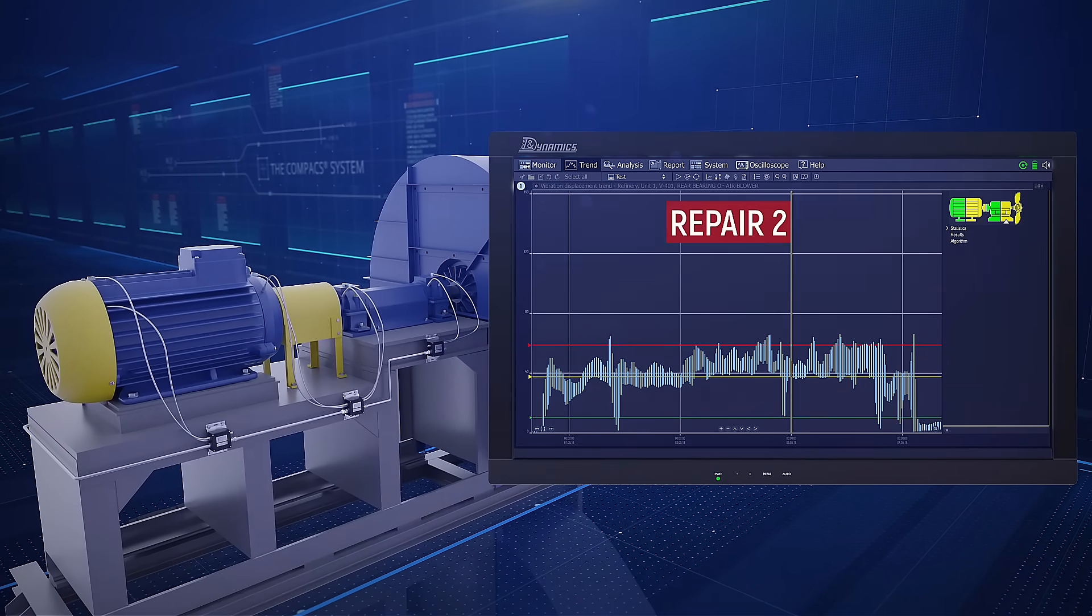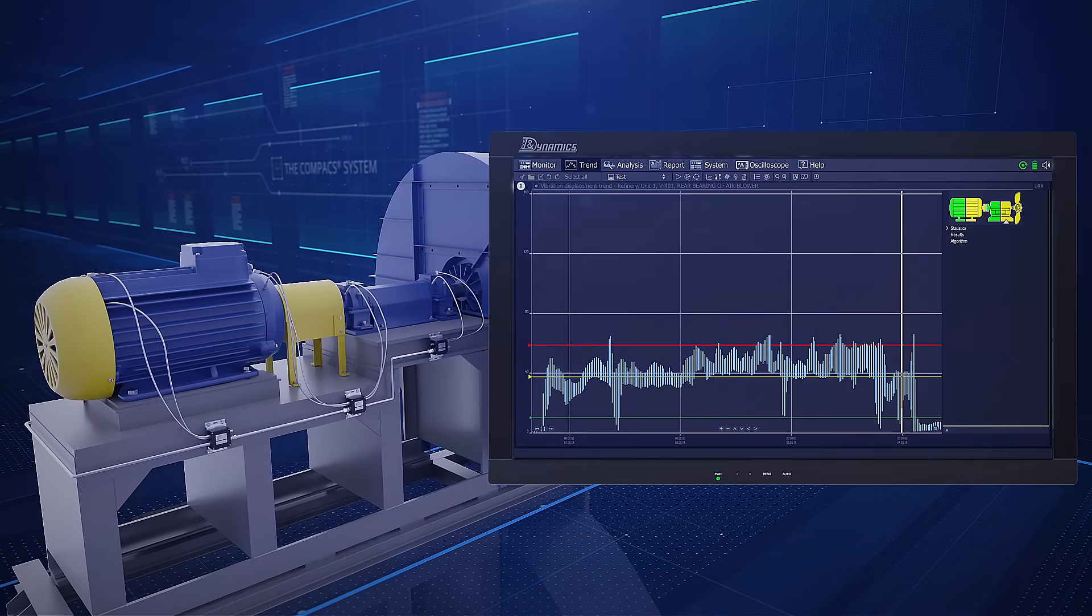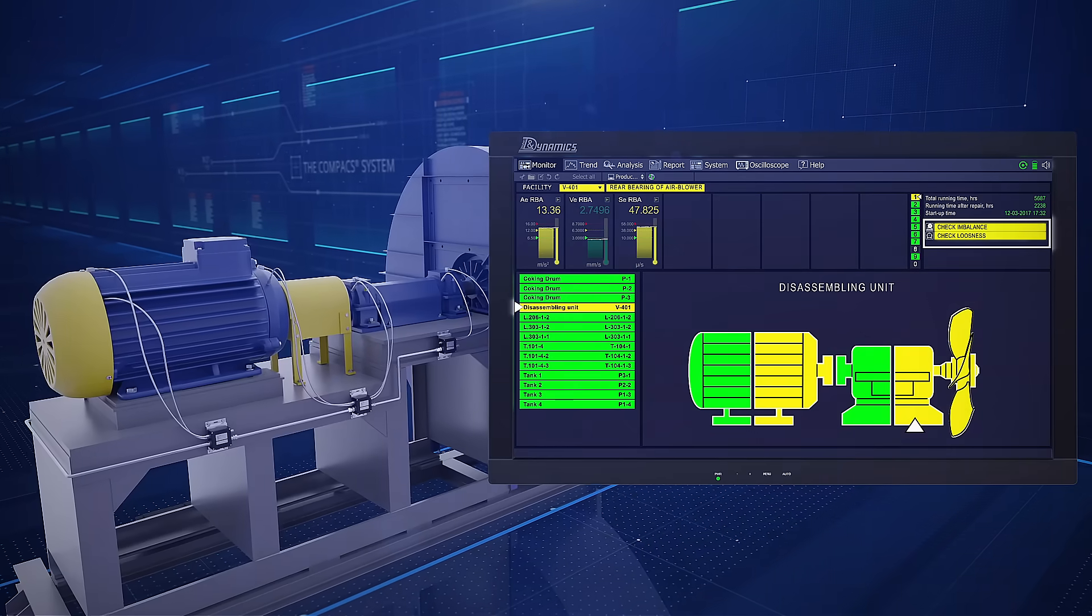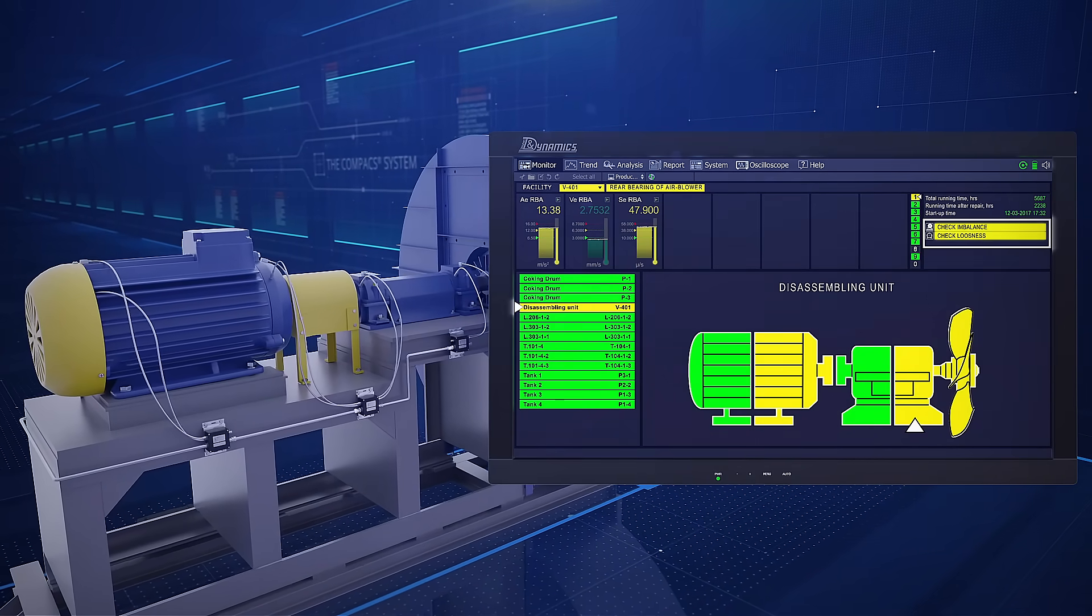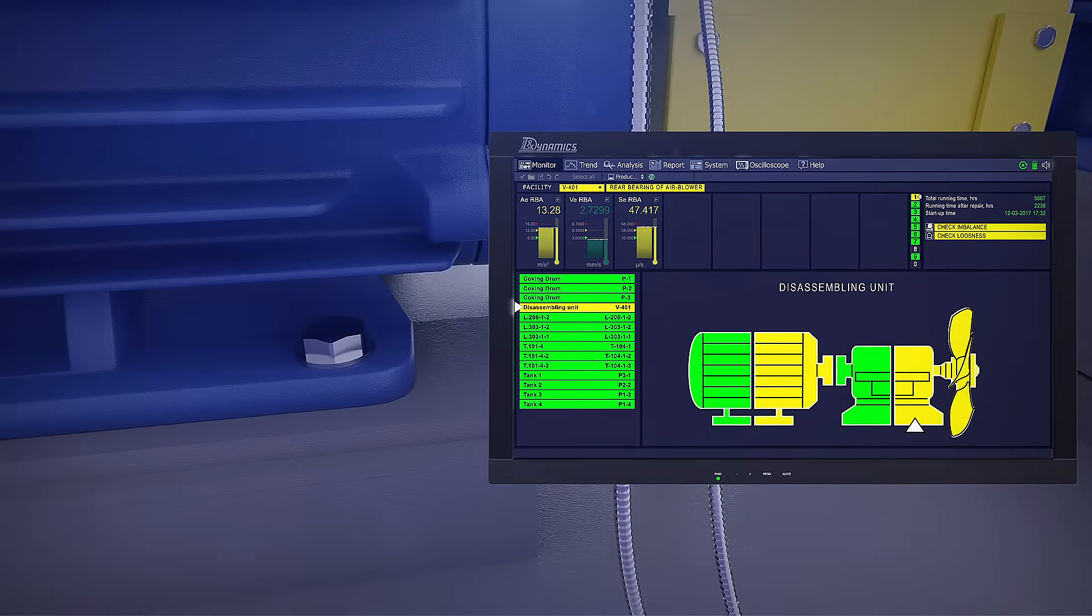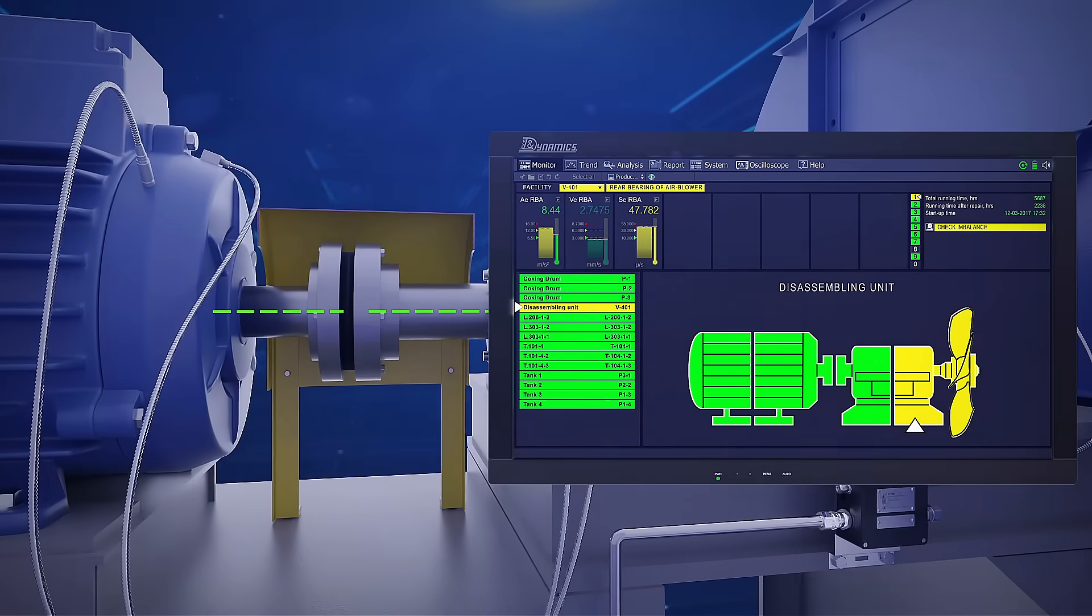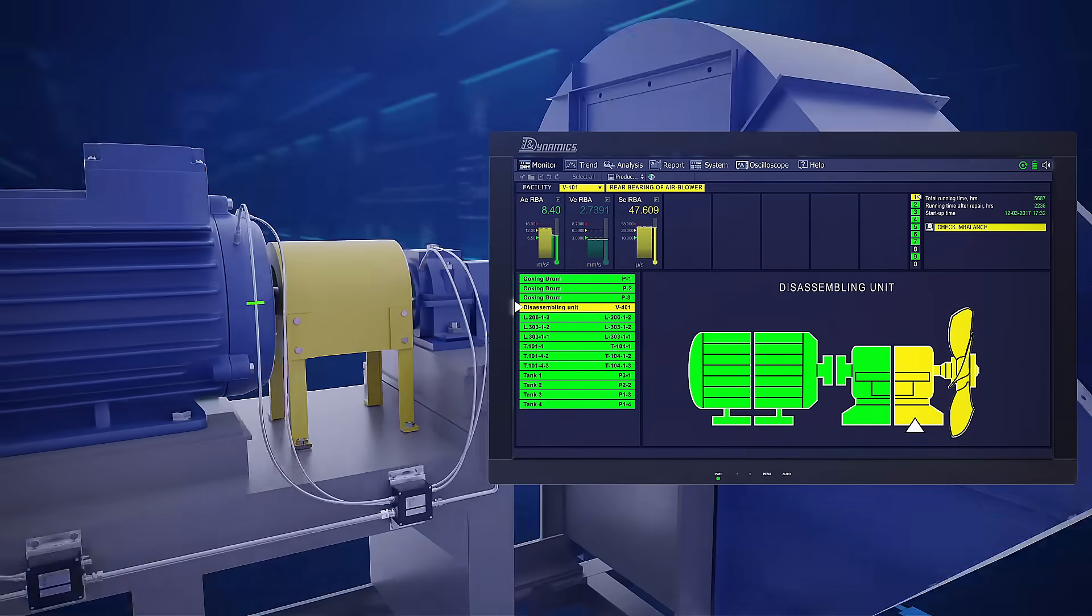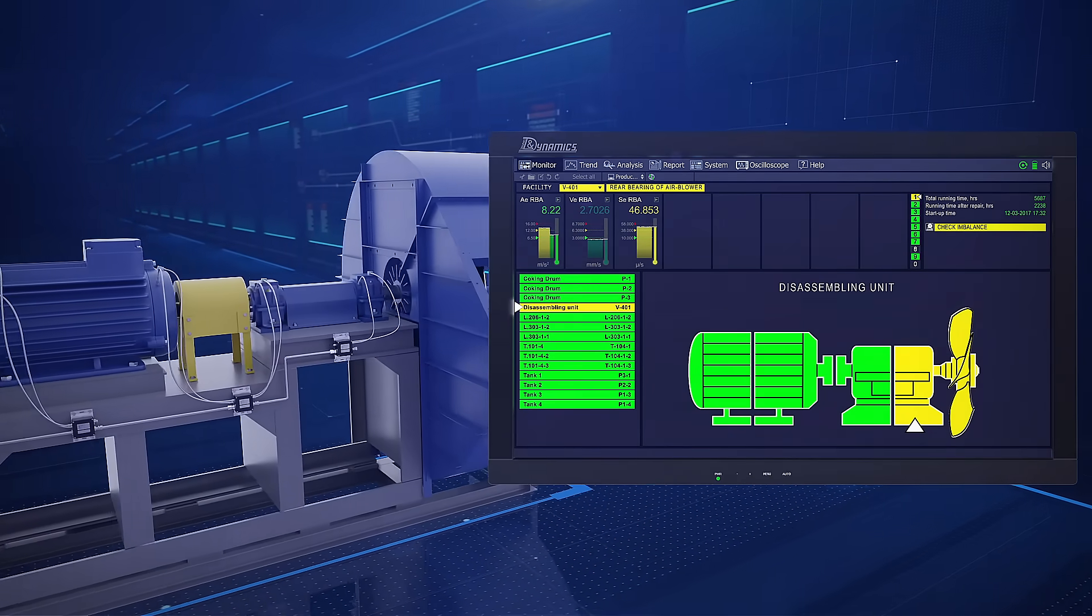Using the COMPACS prescriptions check for imbalance and check for looseness, this included tightening screws and aligning the exhaustor. As you can see, those repairs did not yield the desired result and the machine kept running in the action required state.